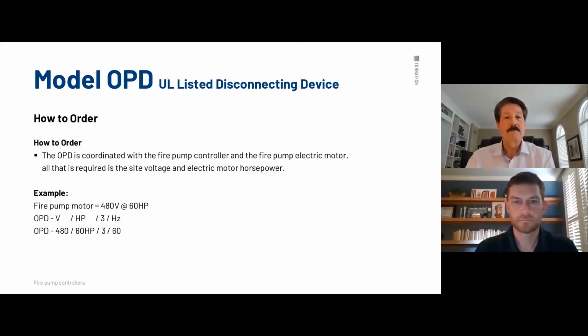It's quite easy to order. As you see, OPD, the voltage. Go up to 600 volt, you need 200, 208, 460, 480. Go up to horsepower, 3-phase, 60 hertz. Again, the OPD is sized not by full load amperage. All that work and calculation has been done by our engineering group at our facility. The OPD is sized by horsepower and voltage of the motor for the pump. It's like your fire pump controller too. Everything is sized accordingly, and all the criteria that's required by code is met. Exactly like I mentioned, 6 times full load amperage, 120 seconds. 10 minutes for 300%. 24 times transient and non-adjustable. So all that's been done. It keeps your life simple.